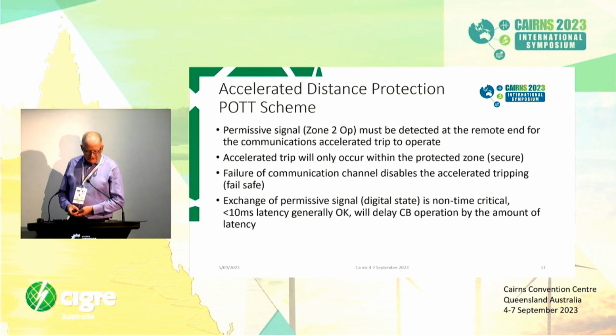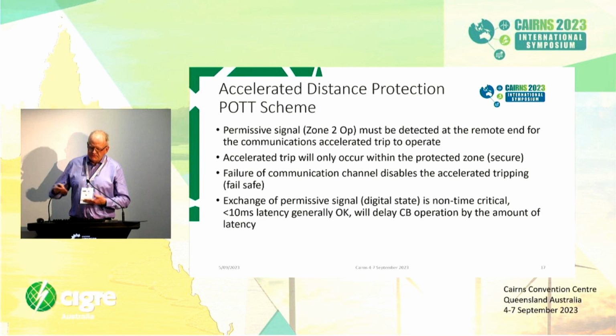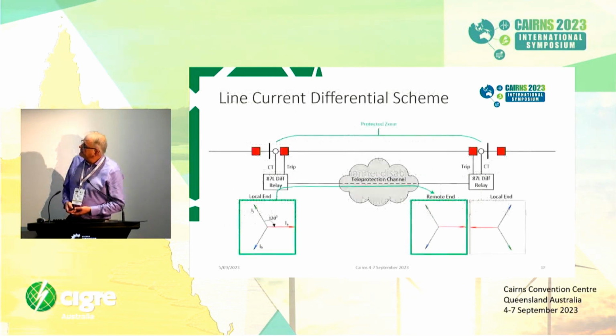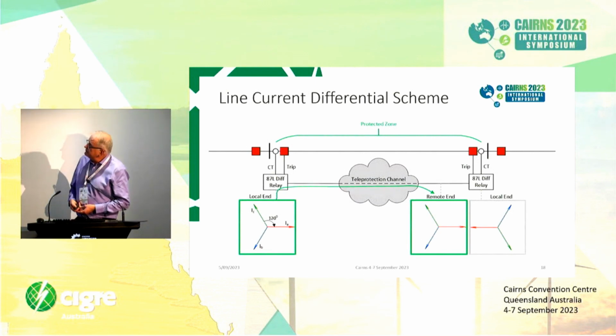And the exchange of the permissive signal is non-time critical. So generally 10 milliseconds latency is still okay. We'll simply delay the actual tripping of the operation of the scheme itself by that latency figure. So the other example I'd like to present is the line current differential scheme.